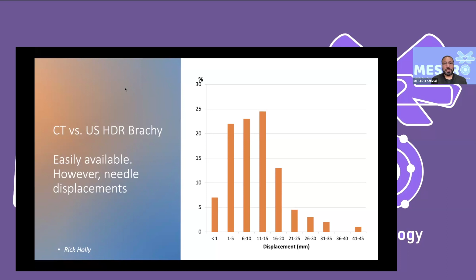On the graph on the right is published data from Sunnybrook that shows needle displacement, which can in some cases be very long, easily up to 15 millimeters, like 1.5 centimeters. Then they have to readjust and retreat, but we're not sure that we are treating what we are seeing. That's the challenge with CT-guided or CT-based HDR. Therefore, most centers, if they have the facility, move to ultrasound-guided brachytherapy. All the equipment I showed you is used for the same procedure. The only difference is that instead of placing the seeds using the needle, we use plastic tubes and connect them with a connector. So this is not much different.